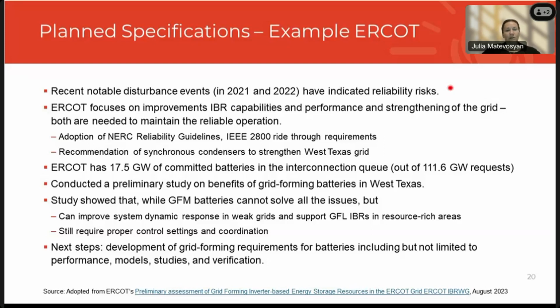So they are looking at solutions. One of the solutions is adoption of IEEE 2800 ride-through requirements. So these are more detailed, more stringent requirements than what ERCOT currently has. There is a recommendation to build synchronous condensers in this area to strengthen the grid. But also, on the other hand, if you look at ERCOT's interconnection queue, there are 17.5 gigawatts of committed batteries. So these are batteries with already signed interconnection agreements, and 2/3 of these batteries already have financial security posted. So it's fairly certain that, say, maybe 70% of this will get built.